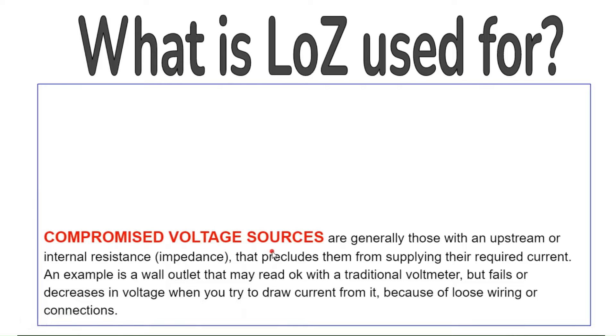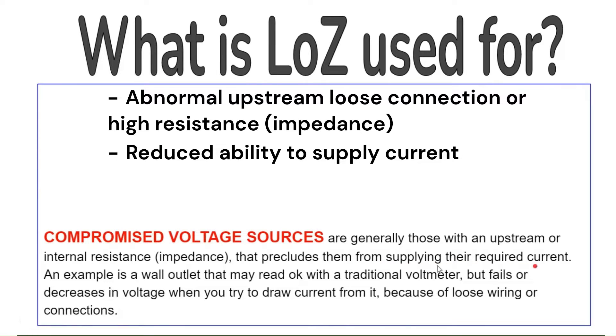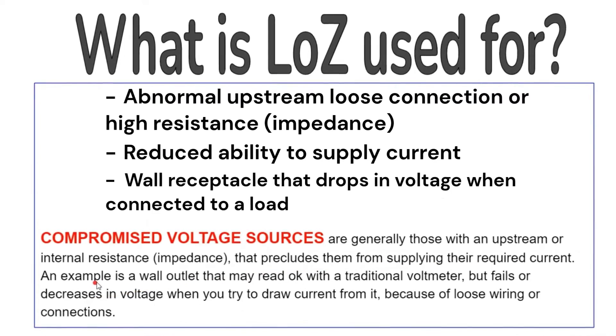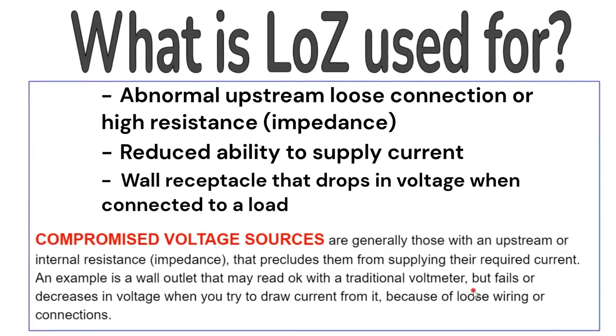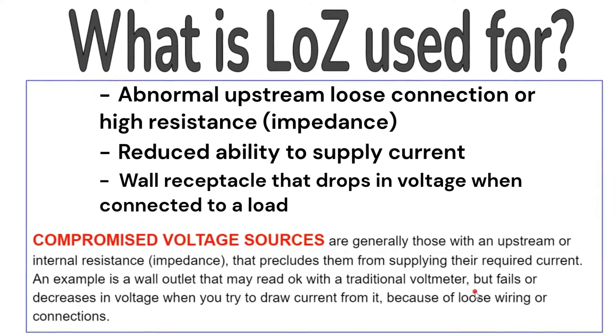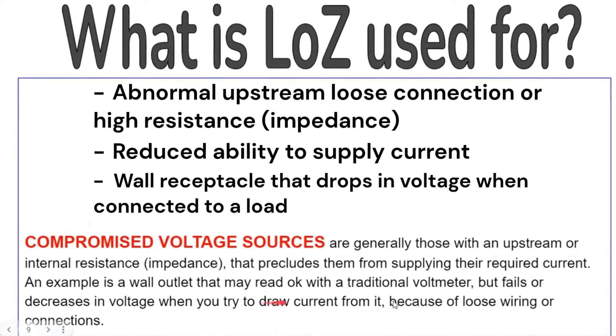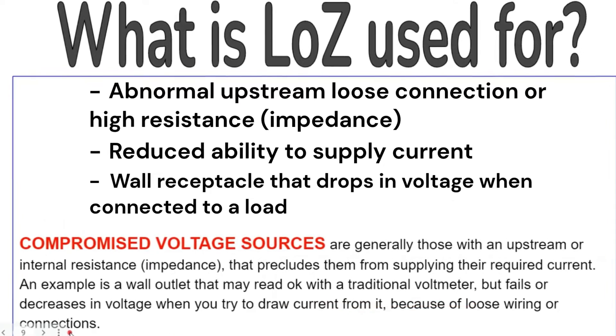Compromised voltage sources, on the other hand, are generally those with an upstream or internal resistance that precludes them from supplying the required current. An example is a wall outlet that may read okay with a traditional voltmeter, but fails or decreases in voltage when you try to draw a current from it, because of loose wiring or connections.